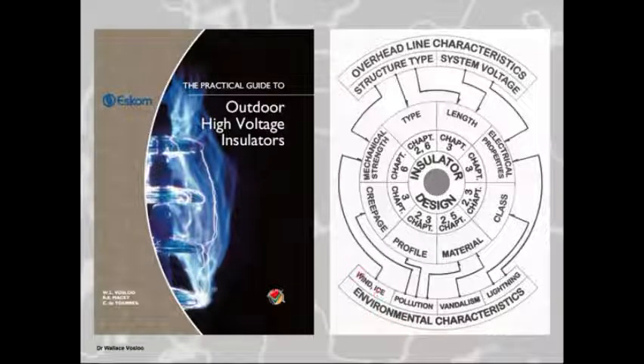Well, if we look at wind and ice loading, you can get ice loading up to over a meter in diameter on a conductor. Can you imagine what it's going to do to the catenary? Can you imagine what effect it's going to have on what weight this insulator must be able to handle? So you will find that the ice will influence the mechanical strength of the insulator, and we've got a whole section on that in chapter 6.